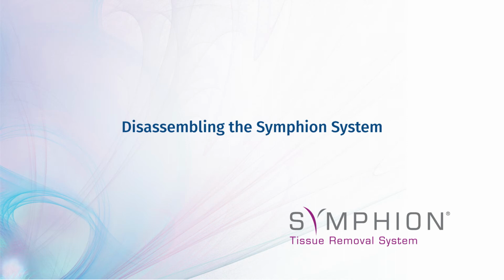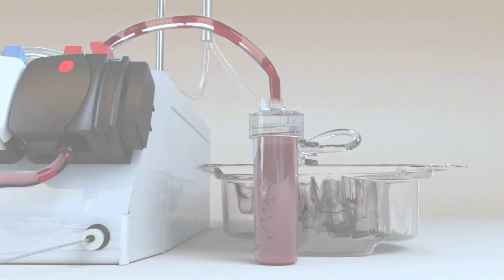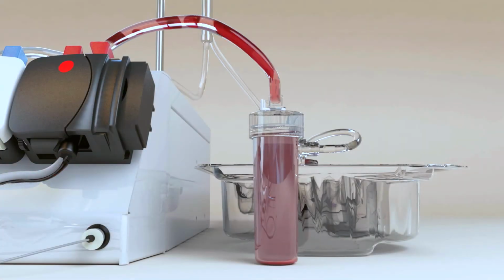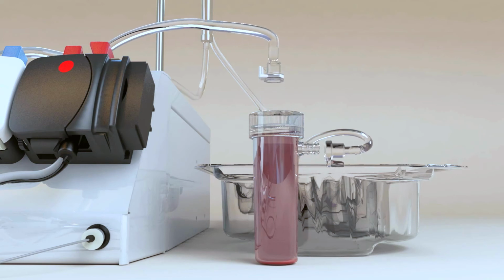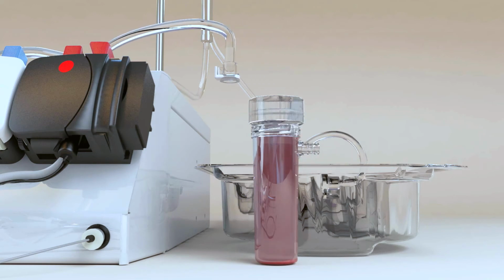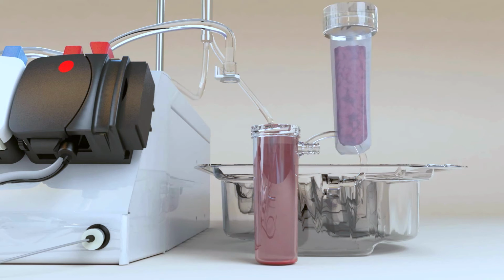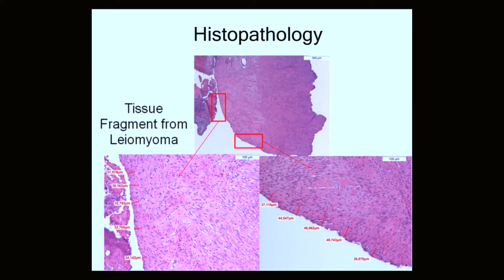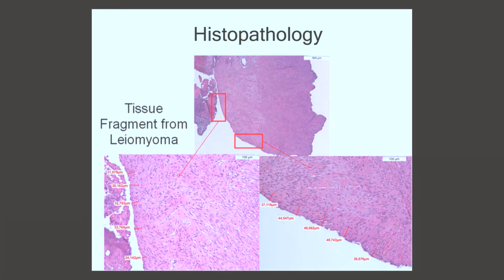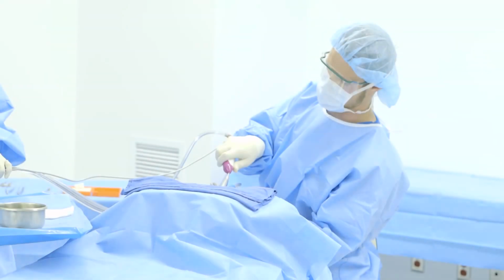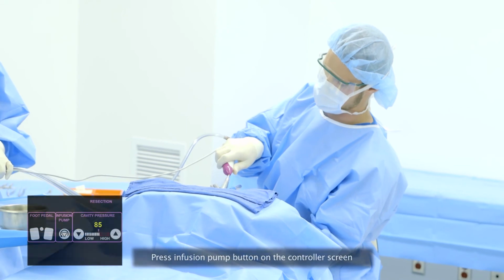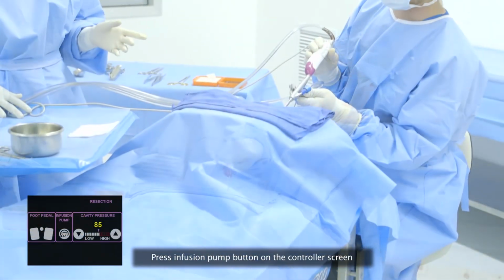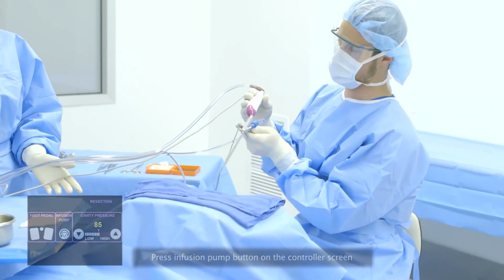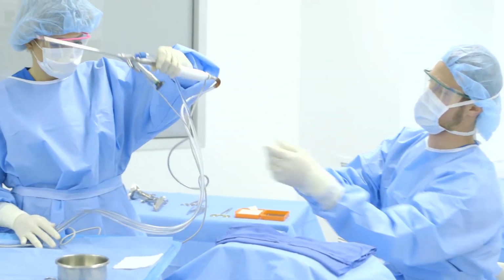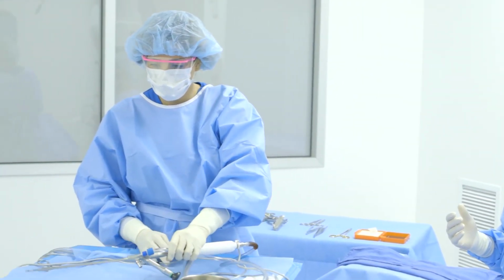Disassembling the Symphion system. The Symphion system is designed to be conveniently disassembled. Viable tissue specimens for histopathology evaluation are contained within the sealed tissue specimen container, which can be detached and sent to pathology. When you are ready to remove the resecting device and endoscope from the uterine cavity, turn off saline infusion by pressing the infusion pump button on the controller screen. Remove the resecting device and the endoscope together from the uterine cavity.